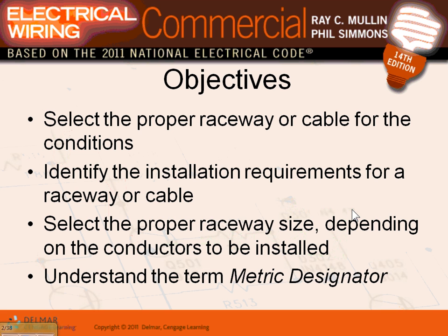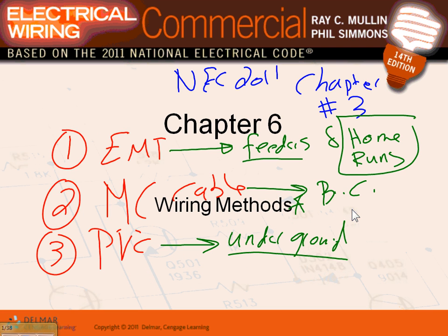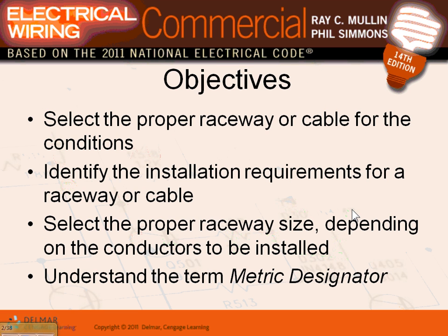Okay, so a couple of things when you read it. We have proper raceway or cable selection. I told you what I think the proper raceway and cable selection is for a commercial building: EMT, MC, and PVC cable. Installation requirements for raceway or cables: where can you use things? The installation requirement, two things, remember. If you are underground, always use PVC. If you're above ground, EMT conduit. This is the major division.